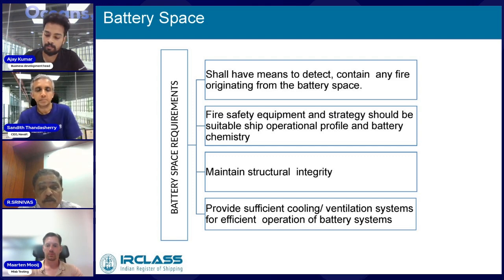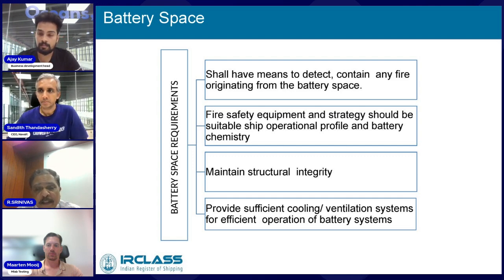We already discussed making the A60 structural integrity so that in case of a fire or thermal runaway, it is contained in the room itself. Why maintain structural integrity? Because you want to contain the fire, you want to prevent the fire. If not able to prevent it, at least contain the fire so it doesn't go out of the room. And we should have sufficient cooling and ventilation systems so that the operational systems are maintained efficiently.